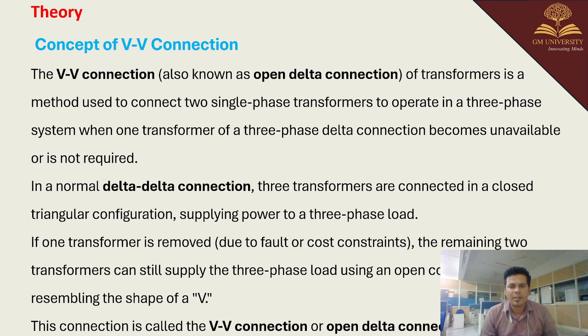In a normal delta connection, the 3 phase transformers are connected in a closed triangular configuration supplying power to a 3 phase load. If one of the transformers is removed due to a fault, the remaining 2 transformers can still supply the 3 phase load using an open configuration, which resembles the shape of a V. Hence it is named the VV connection, or you can say the open delta connection.